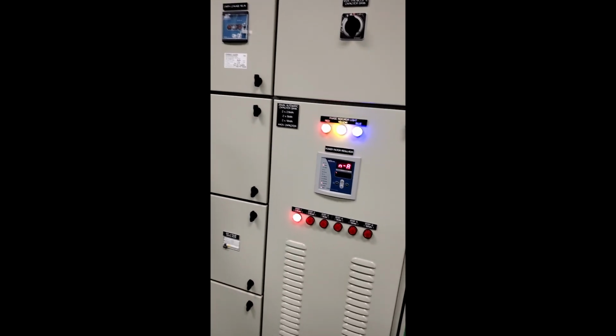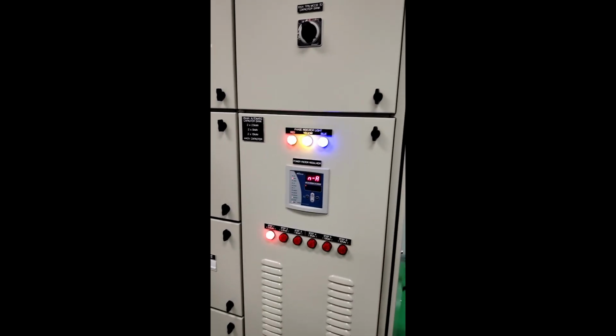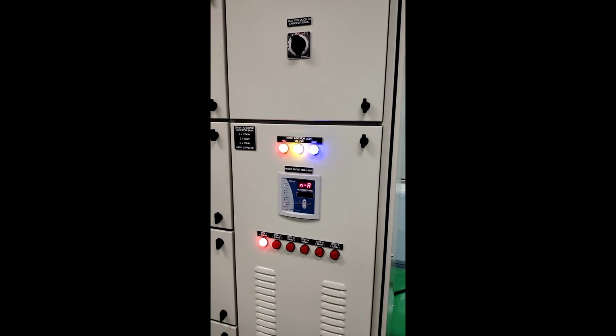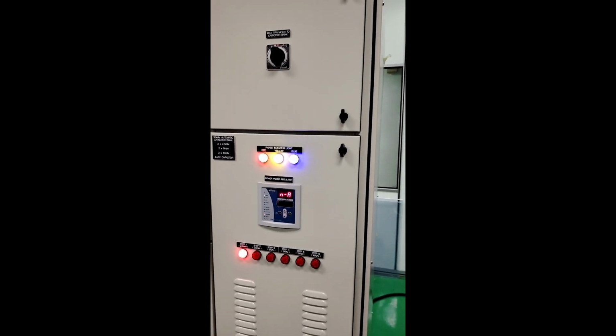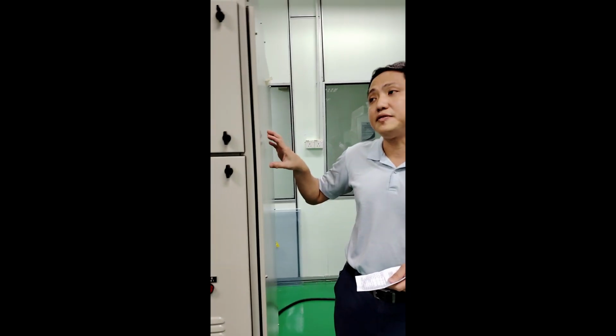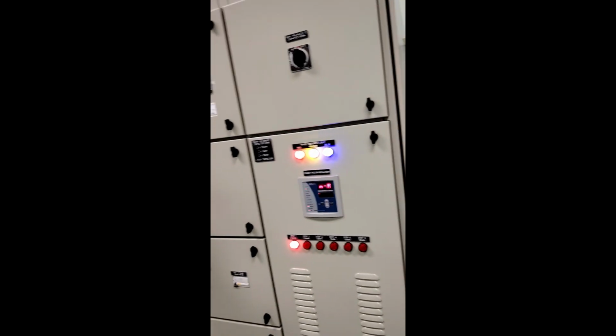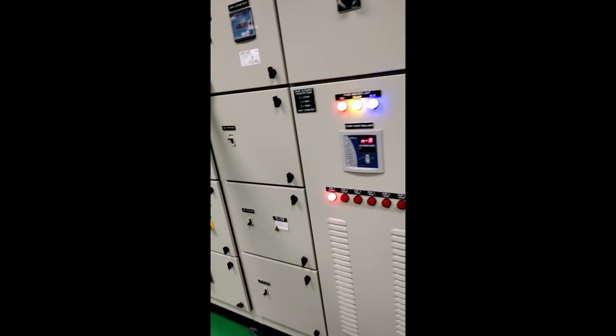How do we define the steps of the capacitor bank, from the 22.5 kVAr until the last step? Normally we design the steps starting from the smallest step we can get, which is 2.5, up to the largest that I've seen, about 40 kVAr. If the capacitor bank needs to be 100 or 200, they parallel up the capacitors.